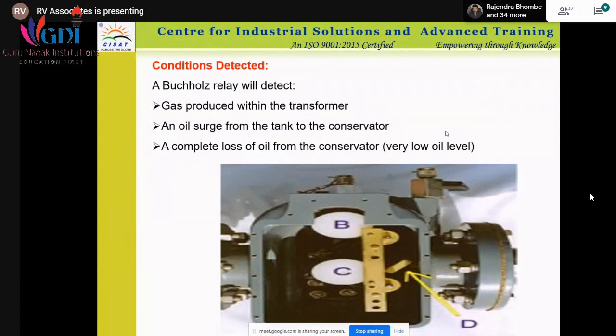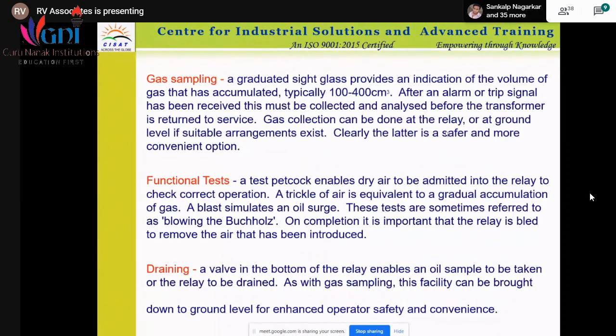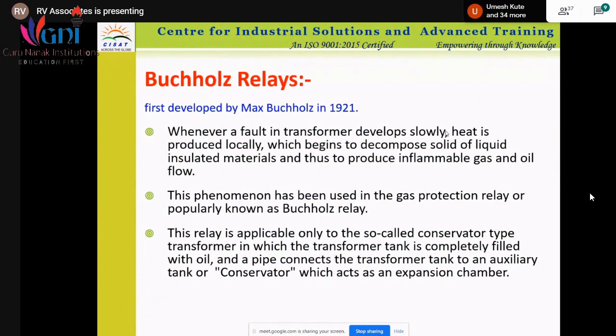Similarly, an oil surge from the tank to the conservator is indicated by the Buchholz relay because we are using the float. Then complete loss of oil from the conservator is also indicated by the Buchholz relay. So all these functions the Buchholz relay is doing. That's why it is very important. Whatever the internal fault is, it will be identified by the Buchholz relay; it will give you the alarm in the first case, and in the second stage it will be a trip. So this is all the theory about the Buchholz relay, who invented it and how the function works. You will get all this information in books.